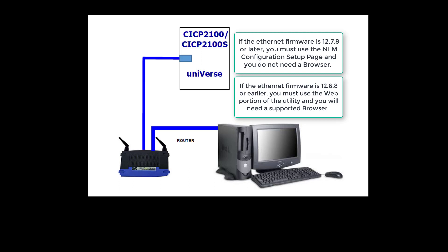To determine which portion of the new utility to use, it all depends on the version of Ethernet firmware in the controller. Very important: if the Ethernet firmware version is 12.6.8 or earlier, you must use the web portion of the utility to update the firmware. If the Ethernet firmware version is 12.7.8 or later, you must use the non-web NLM configuration setup page.